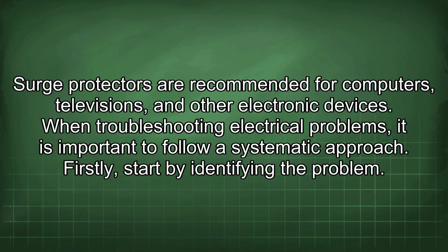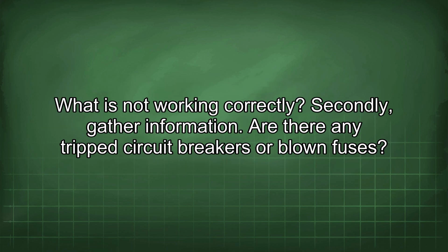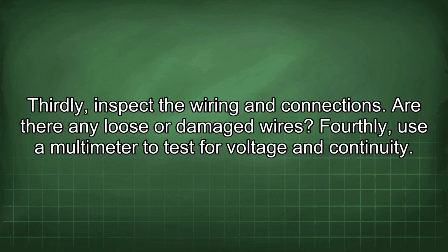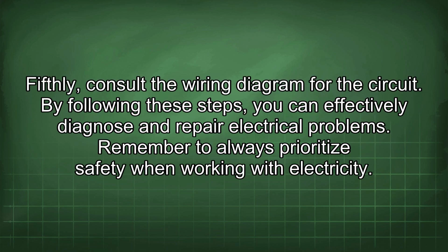When troubleshooting electrical problems, it is important to follow a systematic approach. Firstly, start by identifying the problem. What is not working correctly? Secondly, gather information. Are there any tripped circuit breakers or blown fuses? Thirdly, inspect the wiring and connections. Are there any loose or damaged wires? Fourthly, use a multimeter to test for voltage and continuity. Fifthly, consult the wiring diagram for the circuit. By following these steps, you can effectively diagnose and repair electrical problems.